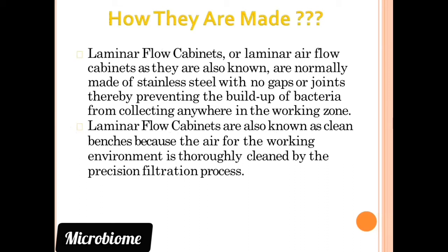Then next, how they are made. Laminar flow cabinets, or laminar airflow cabinets as they are also known, are normally made up of stainless steel with no gaps or joints, thereby preventing the build-up of bacteria from collecting anywhere in the working zone. Due to the presence of stainless steel material, there is no build-up or growth of bacteria most of the time.